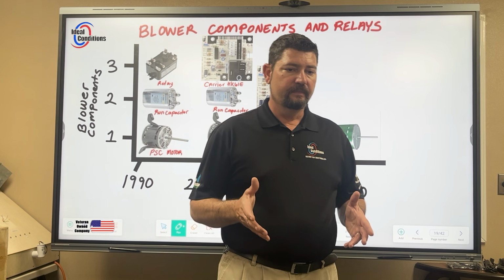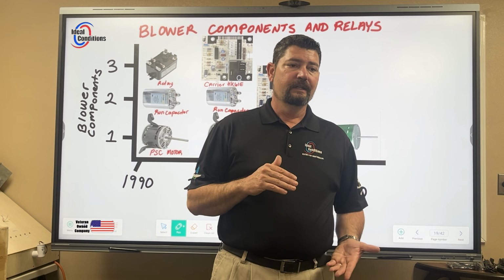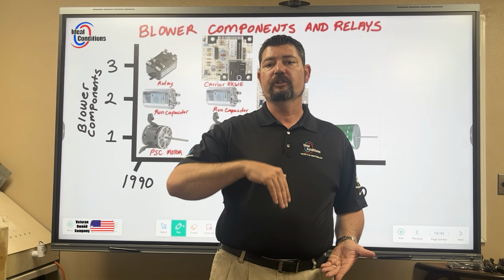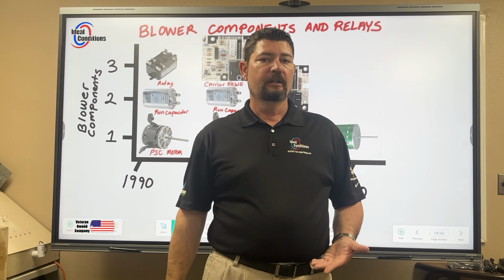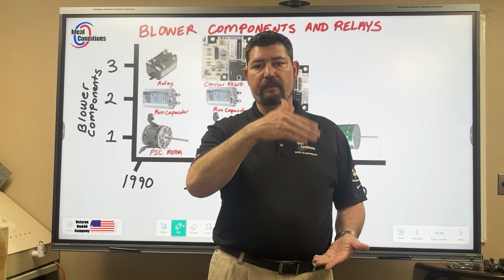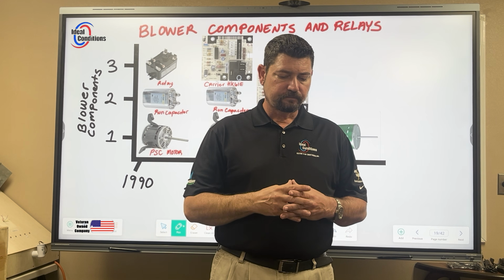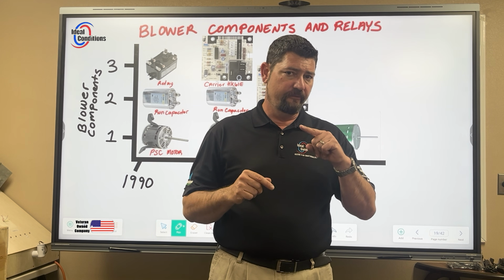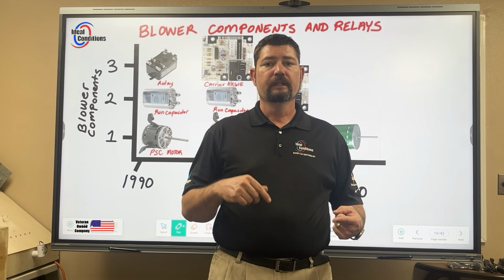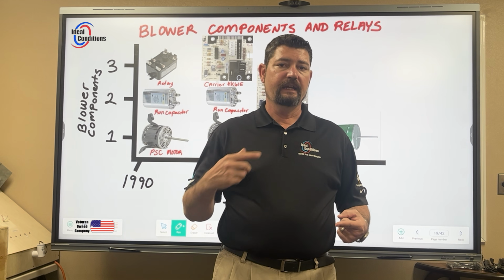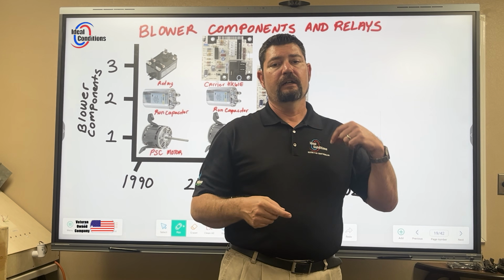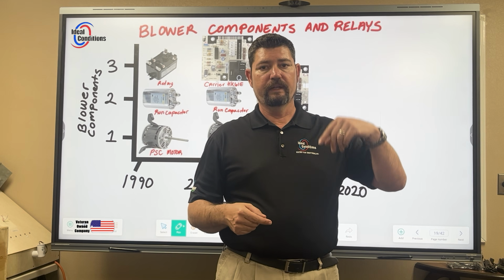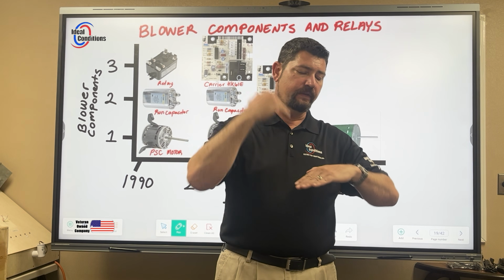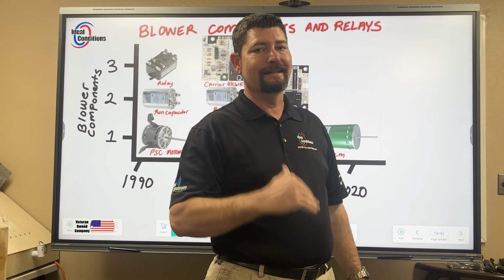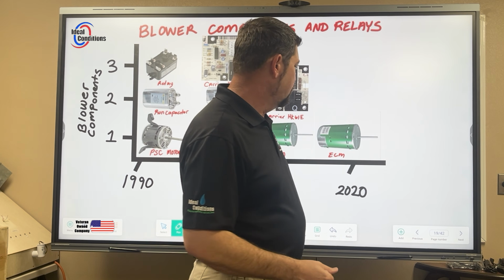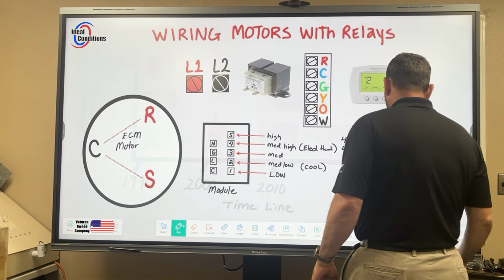So if you want it to run like a medium low, you can't run medium low in conjunction with a heating element. You have to run at a medium or medium high speed. And so that's why they come factory wired to medium low to get more cooling comfort out of it, and a medium high to run in addition with the call for fan with heat strips, because medium low is not enough CFMs. I'm going to go ahead and get right into this.